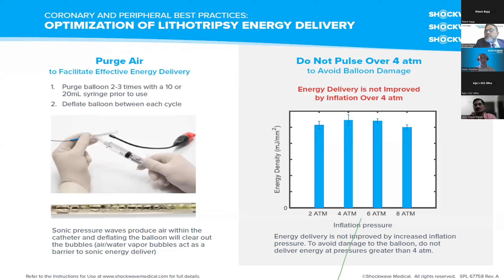The 1-to-1 saline contrast mix needs to be purged 2 to 3 times with a 10 or 20 ml syringe. This, in my short time with Shockwave, has really been driven home to me, for anybody who wants to avoid having to troubleshoot the catheter. This is absolutely critical, not only for the error messages but also for the outcome. Air within the catheter may also give you an error message, but it will also be an issue for the energy that we're transmitting from the emitters into our target calcium, in that it won't be as effective.